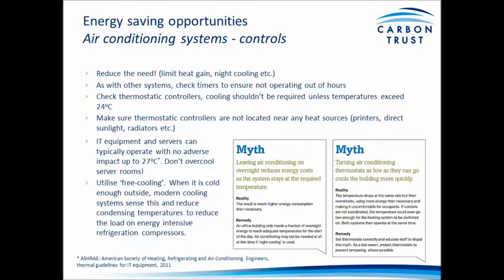A common thing we see with server rooms is that they are overcooled, and common guidance we give is that there is no adverse effect to your IT equipment with temperatures up to 27 degrees C. So don't overcool server rooms. This can be a challenging battle with your IT teams, but it is worth it in the end, as I'll show on the next slide. And then there are cooling systems that can utilize free cooling when it's cold enough outside, and they will reduce the condensing temperatures to reduce the load on the energy-intensive refrigeration compressors in the external plant, and function with effectively free cooling. But your system needs to be capable of this.